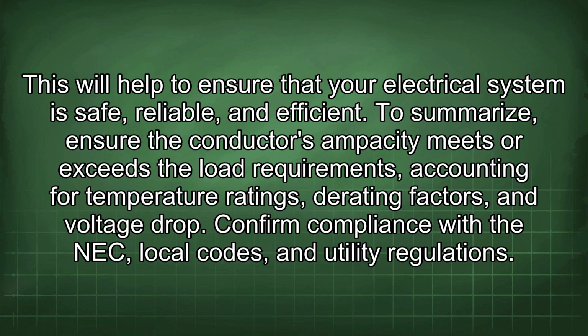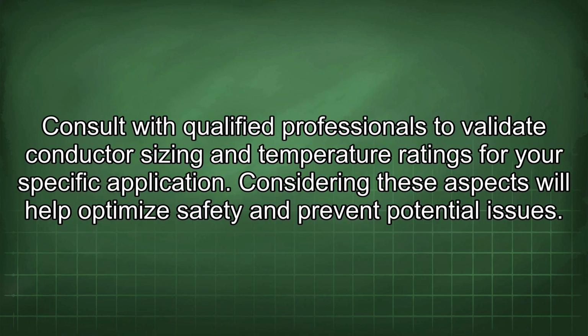To summarize, ensure the conductor's ampacity meets or exceeds the load requirements, accounting for temperature ratings, derating factors, and voltage drop. Confirm compliance with the NEC, local codes, and utility regulations. Consult with qualified professionals to validate conductor sizing and temperature ratings for your specific application. Considering these aspects will help optimize safety and prevent potential issues.